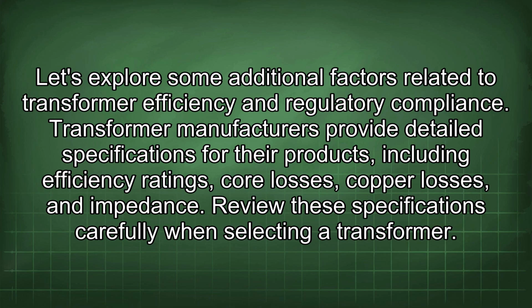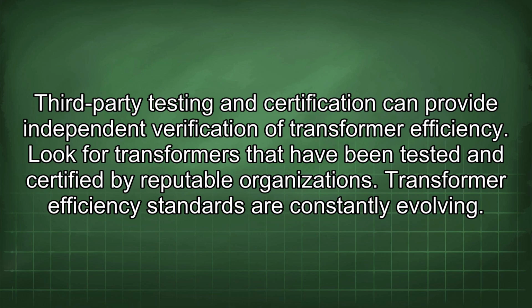Let's explore some additional factors related to transformer efficiency and regulatory compliance. Transformer manufacturers provide detailed specifications for their products, including efficiency ratings, core losses, copper losses, and impedance. Review these specifications carefully when selecting a transformer. Third-party testing and certification can provide independent verification of transformer efficiency. Look for transformers that have been tested and certified by reputable organizations.